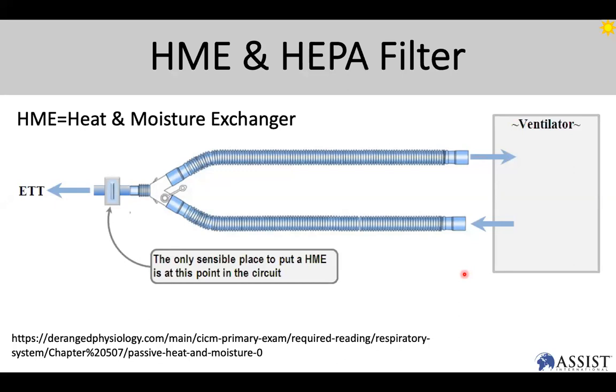Now, you have a combination of this called the HMEF, and you may have seen it. HMEF is a combination of both the heat moisture exchange as well as the HEPA filter. We usually recommend, as per the protocols that they've put out, that if you're treating a highly infectious patient, you want to use 2 HMEF filters in the circuit. One will be attached right after the white piece before it gets to the endotracheal tube. And another one they recommend that we attach to the expiratory limb.